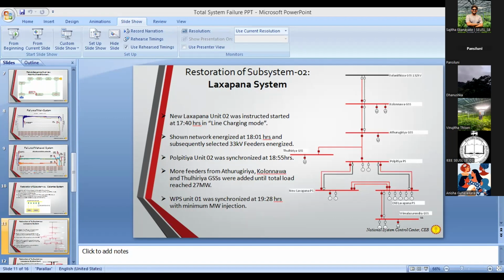There are no consumers because we have already cut off all the 33 kV feeders, but the transmission lines keep pumping reactive power into the system. Then the system voltage will increase rapidly. Then again, whatever machine you energize will be tripped because of the overvoltage. That machine can't absorb that much reactive power, so it will trip. To avoid those two issues, restoration has to be done part by part.